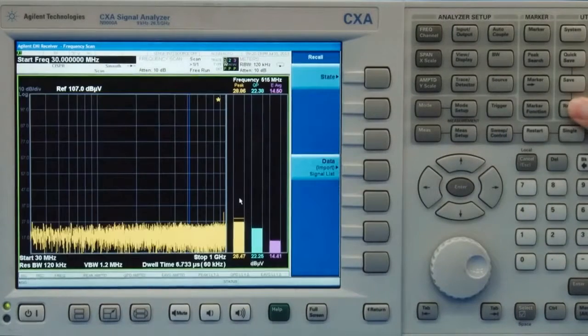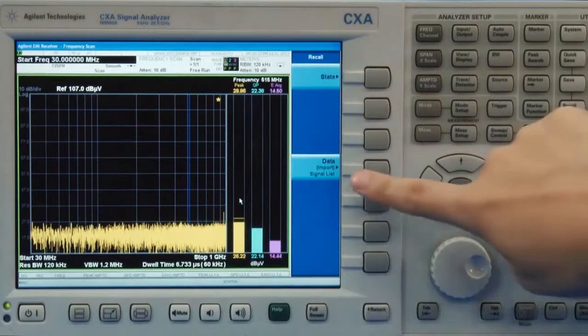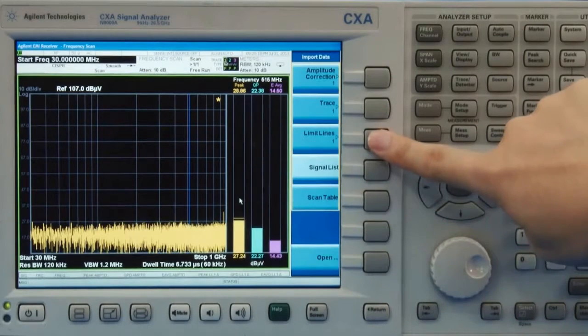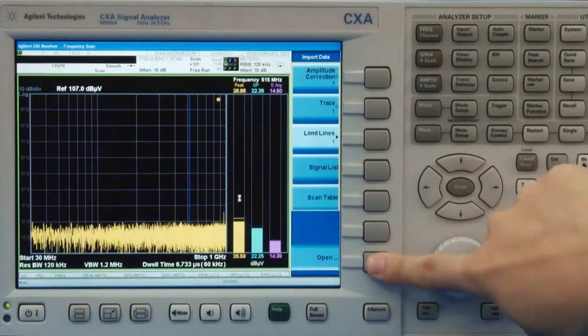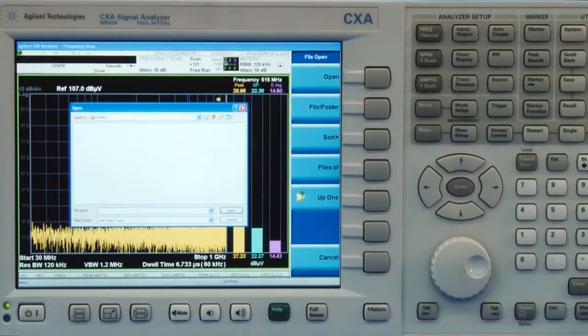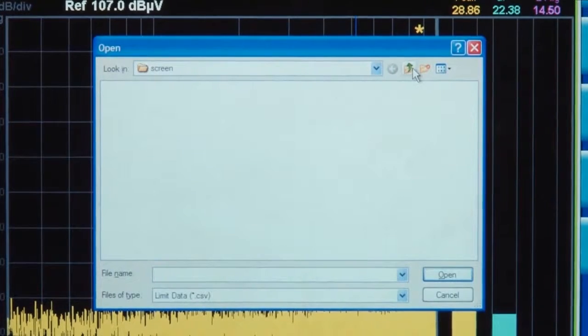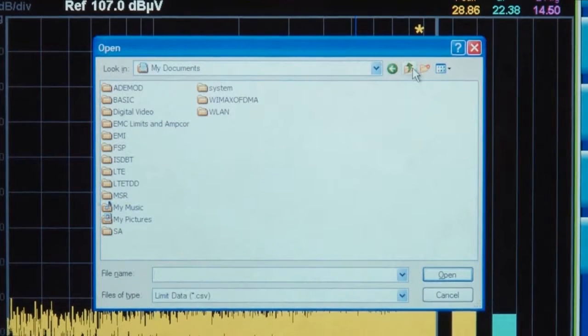When conducting a far-field EMI pre-compliance test, we can recall the limit lines which are pre-installed in the instrument according to the EMC standards. For instance, in this case, we choose the EN55022 standard, which applies to laptops.